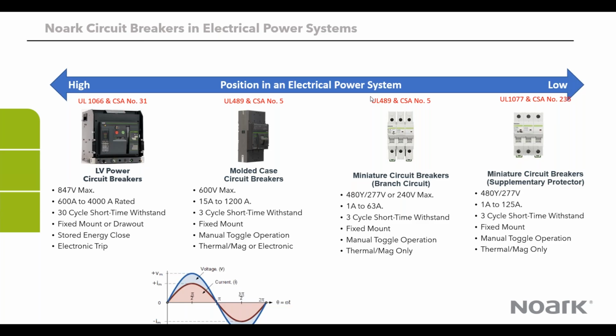So we've got all of this lineup of products that are situated in the electrical system. And to my far left is the UL 1066 power circuit breaker. Today we have an offering up to 4,000 amps, both for fixed and draw out. They are a stored energy close type of breaker, so it uses spring stored energy to be able to close the breaker. Just because the frame is larger, a toggle operation might be difficult here compared to a molded case that has a toggle. So this stored energy close allows you to close the breaker in a smooth and effective way. It's also electronic trip, and it's a 30-cycle short time withstand.